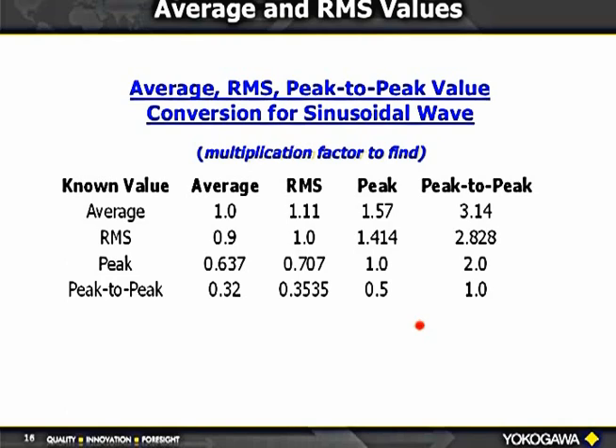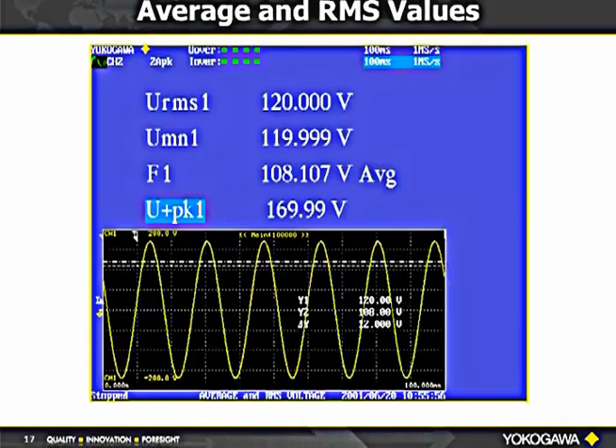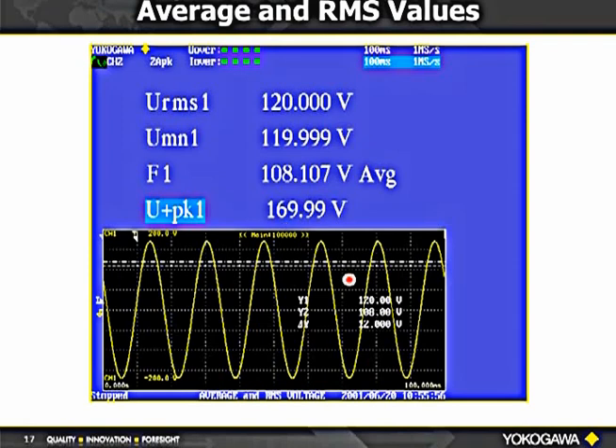Here's a screen from the power analyzer set up on a calibrator. We're reading 120 volts RMS (U RMS1) on element number one. U mean is the mean value scaled to RMS — equivalent to what a moving-coil meter would read. The peak value is 169.99, approximately 170 volts. Looking at the sine wave waveform, the RMS value shows at 120 with the top cursor and the half-cycle average mean at 108, showing their relationship on the waveform.